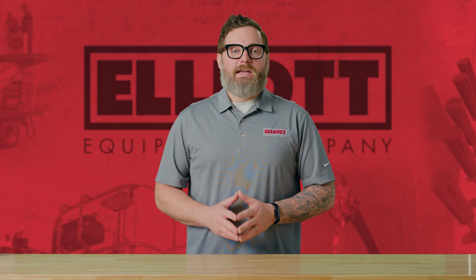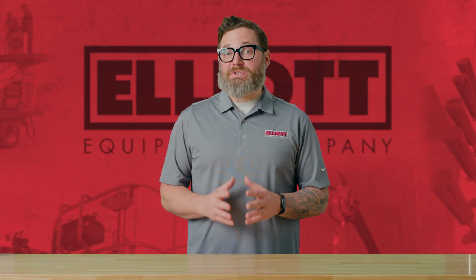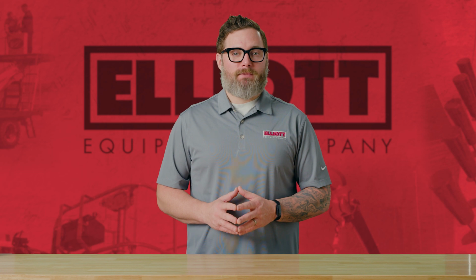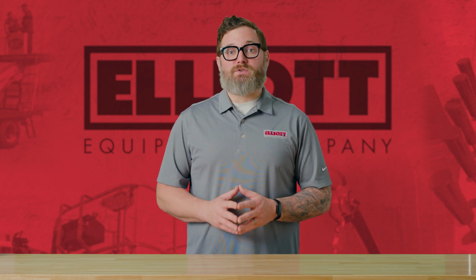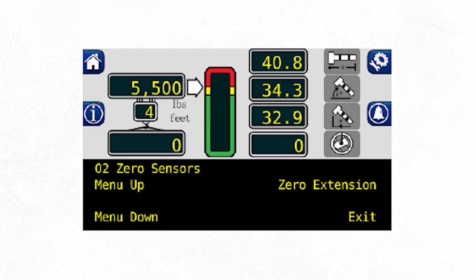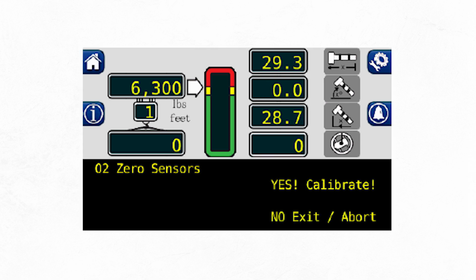fully retracted. Now press the menu up button until 02 Zero Sensors is reached. Then press the 02 Zero Sensors button one time and the screen should look like this. After that, you're going to press the Zero Extension button and that will bring up a prompt. Press the Yes Calibrate button to calibrate to 0.